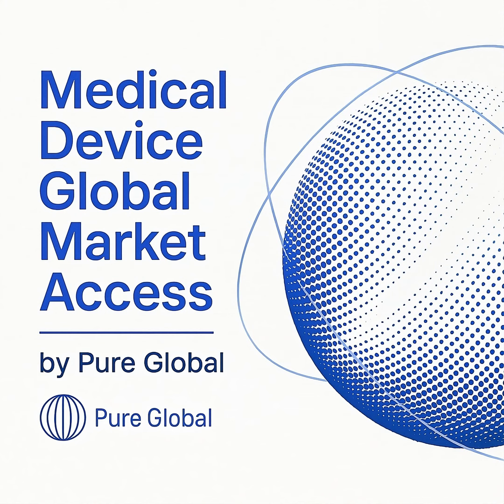This brings us to the core question: how does a CE mark affect the MDEL process? While your CE marking and the associated technical documentation are vital for European market access and can be leveraged for a higher class MDL application, the CE mark does not provide a shortcut or exemption for the MDEL. Health Canada operates its own regulatory framework. The MDEL application focuses on your company's procedural readiness, not the technical conformity of the device.